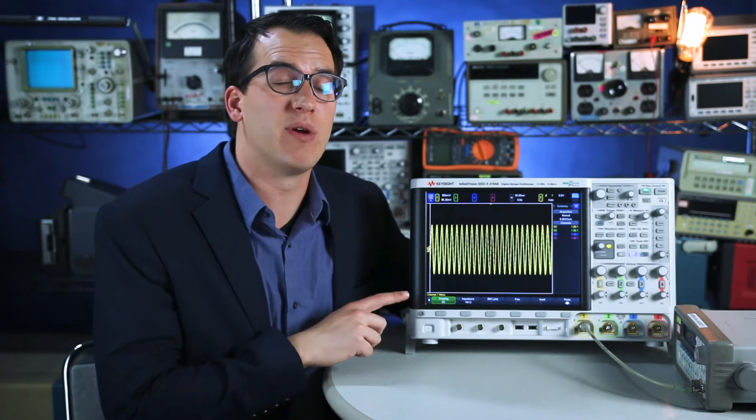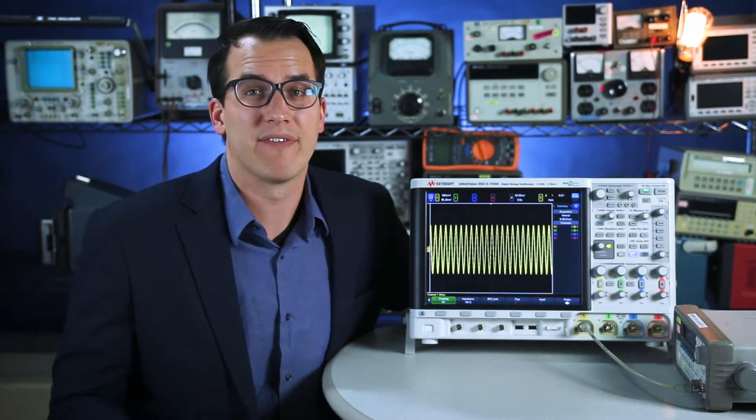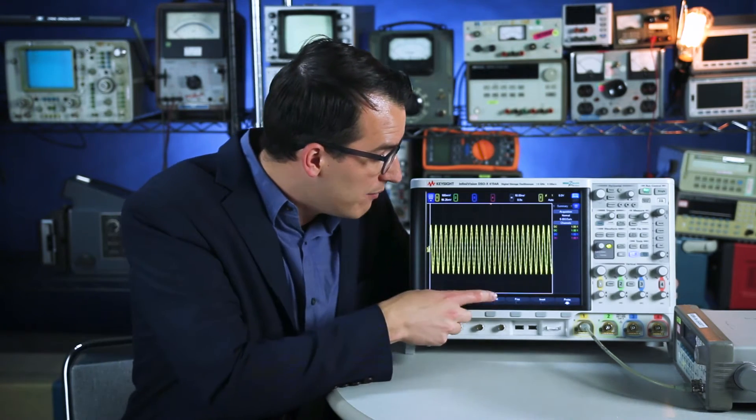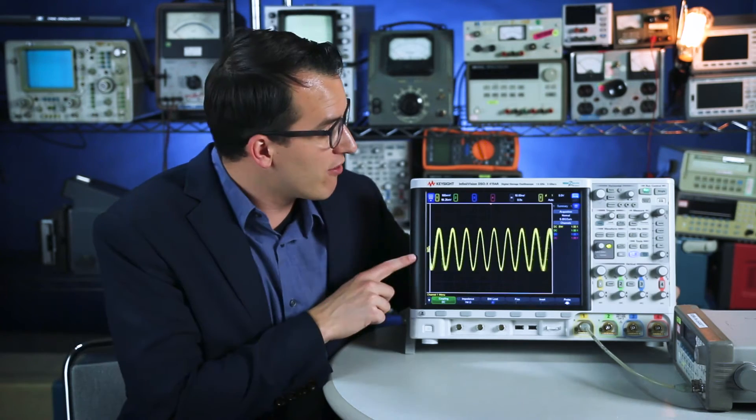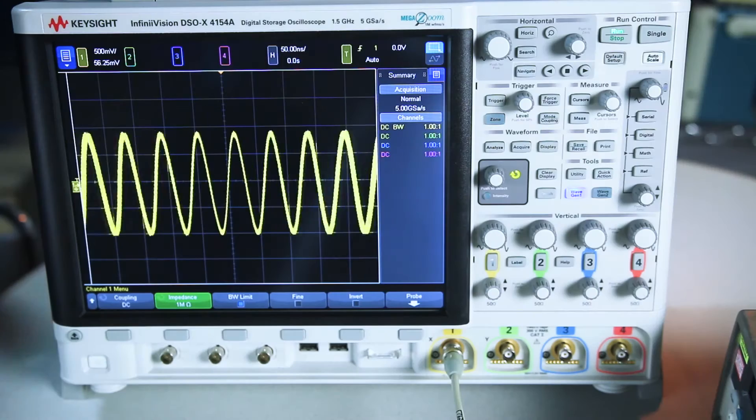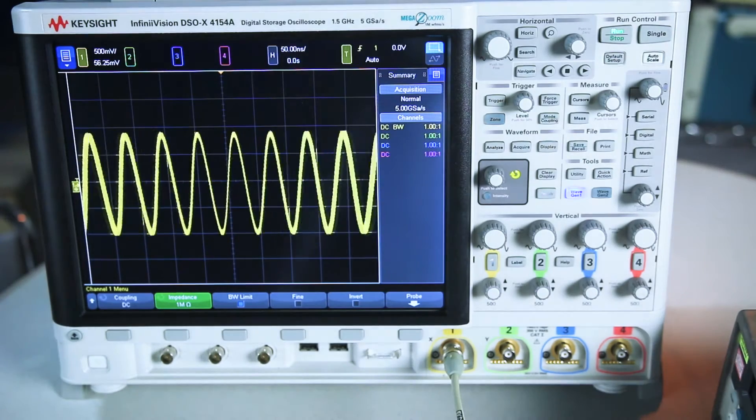I have on screen a signal sweeping from 20Hz to 60MHz and clearly with my 1.5GHz oscilloscope I'm having no trouble seeing that signal. But let's turn on a 20MHz bandwidth limit. So I'm going to now emulate a 20MHz scope. This is what that signal would look like if I had a 20MHz scope. Notice how it gets smaller and smaller the higher the frequency goes.